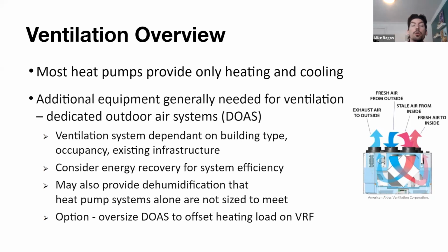And lastly, and this is an important note, in another way of how we design in cold climates, an option to offset the heating load in order to allow your VRF system to be the lowest tonnage possible is to oversize your DOAS system. What that would mean is that if your DOAS system is oversized, it's more than enough to provide that heated outside ventilation air to the space. Because you're getting a great deal of heat from your DOAS system, we're not going to have to worry as much about those derates in the absolute coldest parts of the year, because your DOAS would then be used to pick up whatever derates your heat pump system may not be able to pick up. So that's an option that we consider when we're taking a look at the whole of a building's HVAC system and how we could size it accordingly.